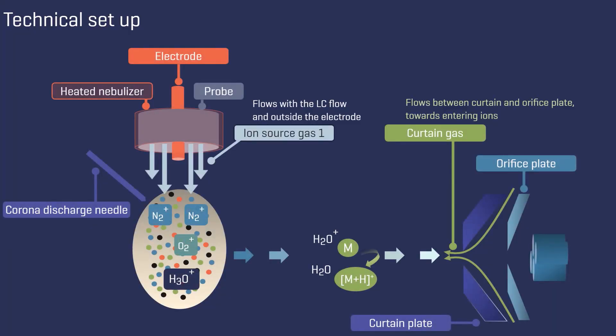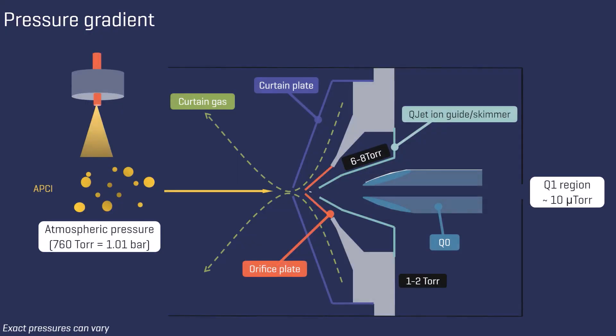This schematic illustrates the technical setup of APCI sources, which enables the chemical ionization process. The transfer of the LC flow into the gas phase is aided by the heat and a gas flow in the heated nebulizer. As within the ESI ion source setup, ions undergo a pressure gradient as they travel from ionization at atmospheric pressure to their entry into the mass analyzer.